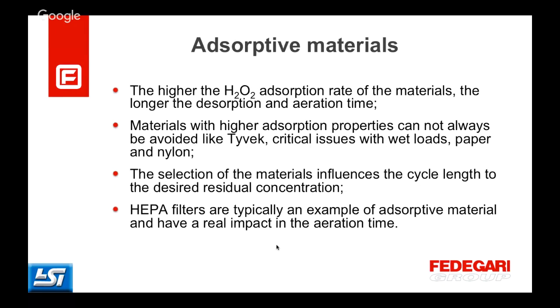Okay, here it's important to mention that Tyvek could be a problem with hydrogen peroxide. Tyvek is a porous material. You know, you use Tyvek bags also to make sterilization, and it is permeable as well to the hydrogen peroxide vapor, and this membrane keeps quite a high quantity of hydrogen peroxide in the container in which the Tyvek is the lid. So the aeration is almost impossible with the Tyvek lid, and this has to be taken into account.